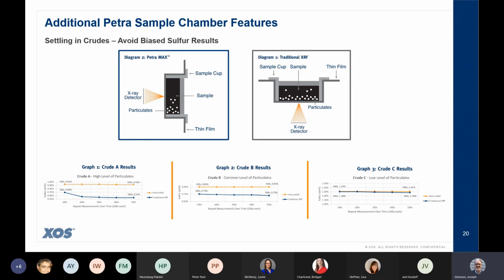Some data down below in 3 graphs. Basically, it's 3 samples with varying degree of particulate concentration. On the left, it's a high particulate sample. You can see with traditional XRF, we're talking about a sample coming out at 0.54% sulfur. With the Petra MAX in that vertical chamber, without the interference, it's picking up 0.93% sulfur. That's quite a difference. That's a problem.